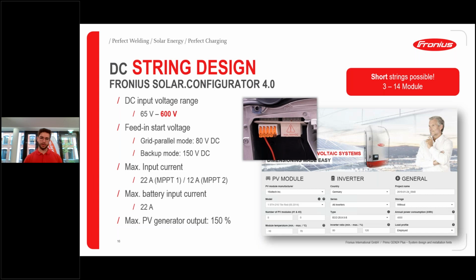And all of our products, also our previous Snap inverters, have the ability to oversize them, as well as our GEN24 Plus device, of course. So also the Primo here is able to configure up to 150% of over-dimensioning on the DC side. So if you pick, for example, a 10 kilowatt device, you can do 15 kilowatt peak on this product. So this is what it means with over-dimensioning without any warranty losses.